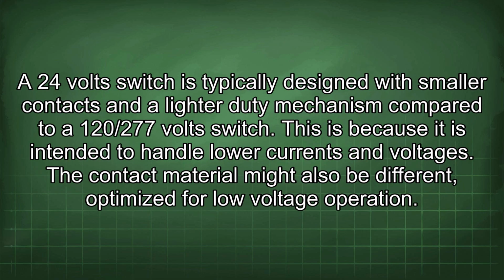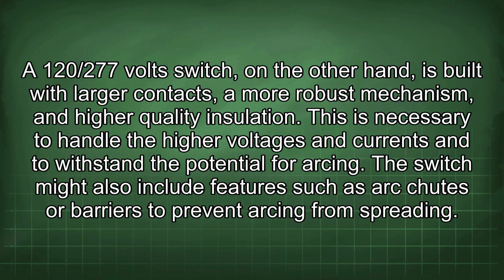A 24-volt switch is typically designed with smaller contacts and a lighter duty mechanism compared to a 120/277 volt switch. This is because it is intended to handle lower currents and voltages. The contact material might also be different, optimized for low voltage operation. A 120/277 volt switch, on the other hand, is built with larger contacts, a more robust mechanism, and higher quality insulation. This is necessary to handle the higher voltages and currents and to withstand the potential for arcing. The switch might also include features such as arc chutes or barriers to prevent arcing from spreading.